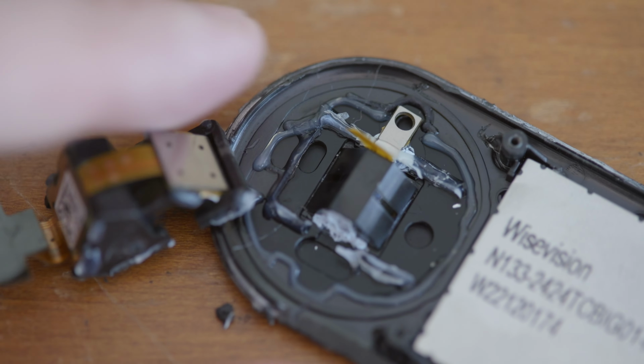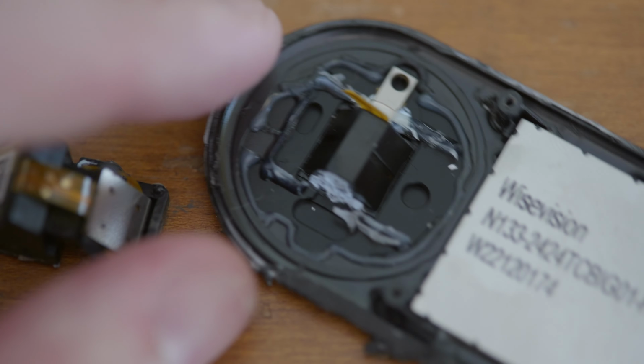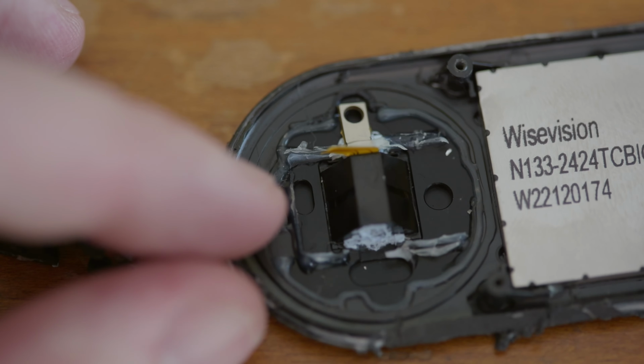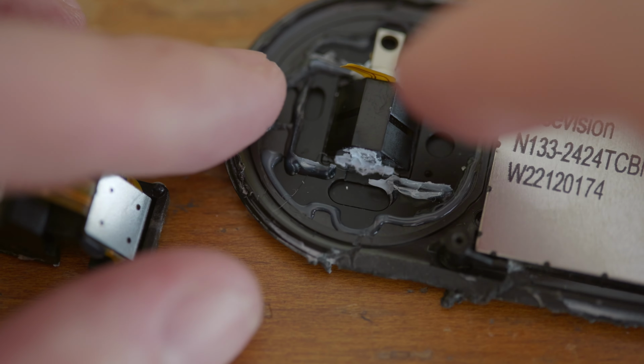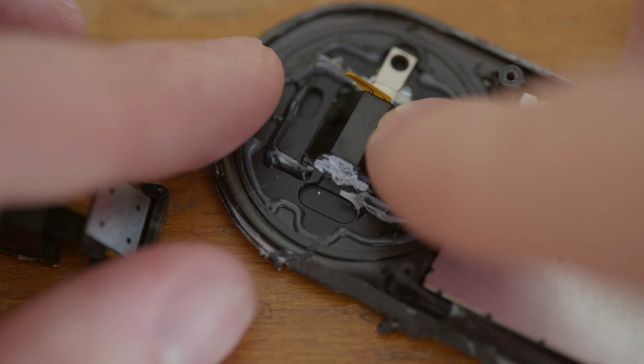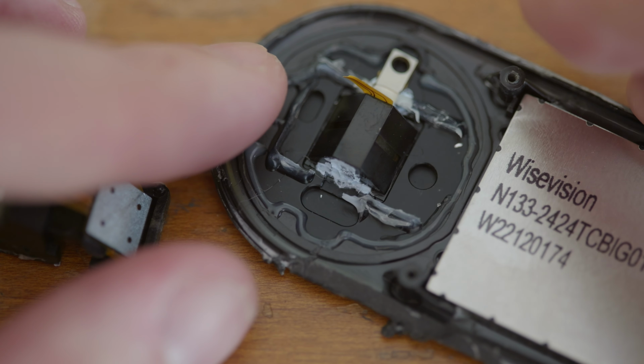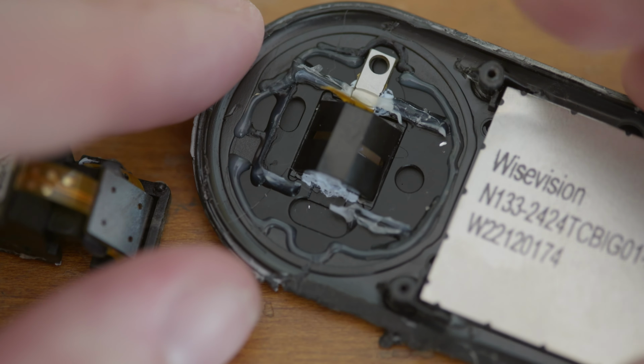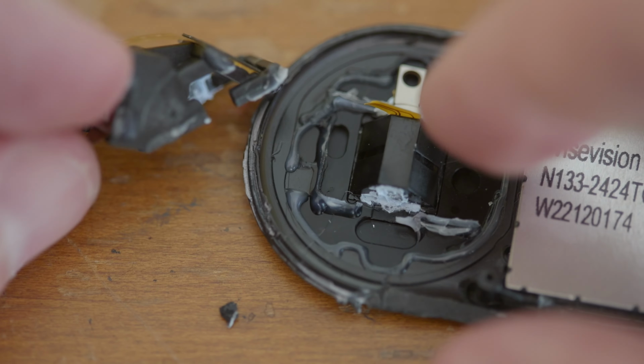And what we've got, it looks like we've got an optical prism right here. And you can see it's got narrow slits to let light through. I believe this piece coming off is probably the probe for temperature sensing, because this thing does adjust its calibration for the temperature of the liquid that you're looking at. So there's your optical prism, and here is the inside of the sensor.